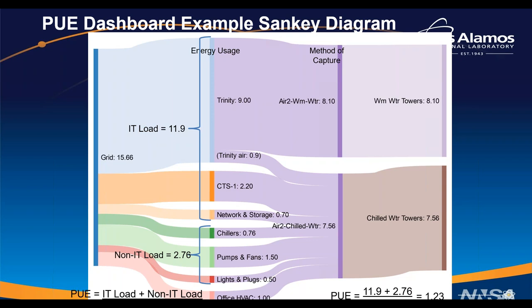We're bringing 15 megawatts in from the grid. The top three streams represent our IT load, about 12 megawatts. The green stream and the first red stream represent the non-IT load. So the IT load is our Trinity, our big supercomputer, commodity technology system one, and also network and storage, and then chillers, pumps, fans, lights and plugs are the non-IT load.